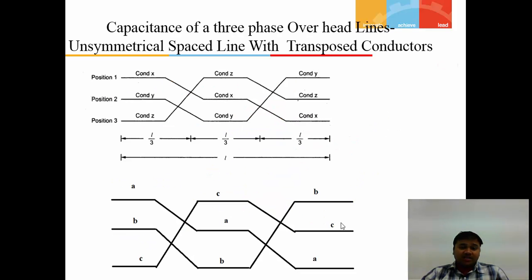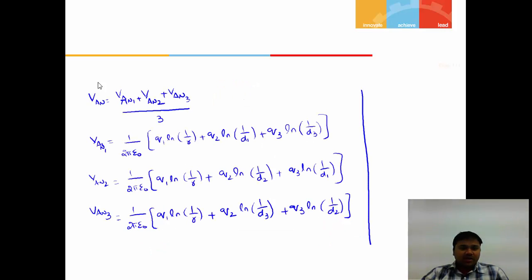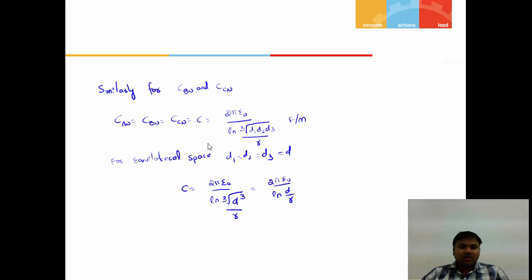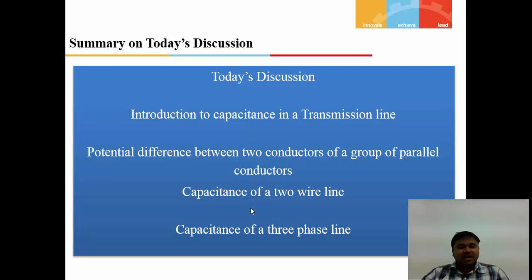If the conductors are transposed — meaning each conductor periodically changes its position — the transposition is analyzed in three steps, computing V_AN1, V_AN2, and V_AN3 at each position and taking the average. For equilateral spacing where D1 = D2 = D3 = D, the capacitance simplifies to C = 2π ε / ln(D/r). For non-equilateral spacing, C = 2π ε / ln(∛(D1·D2·D3)/r). These are the key formulas. That concludes today's brief overview — thank you for watching.